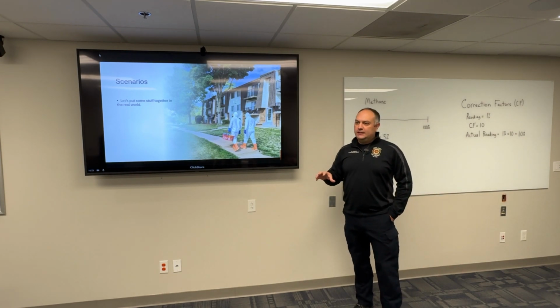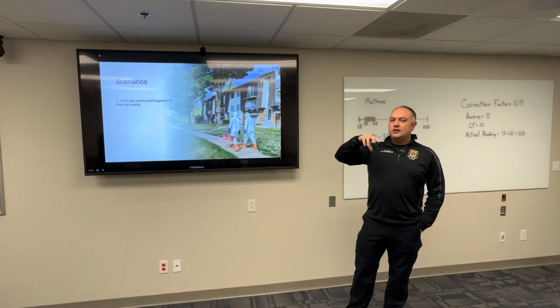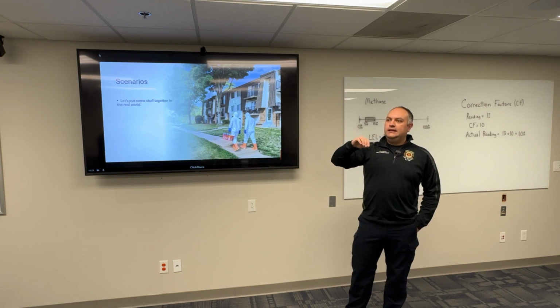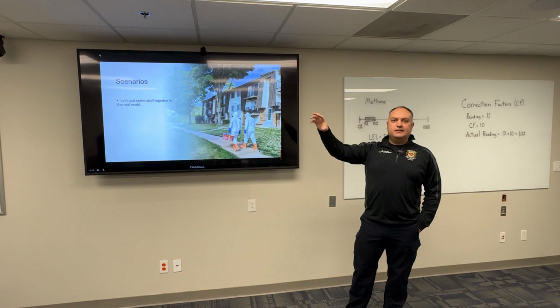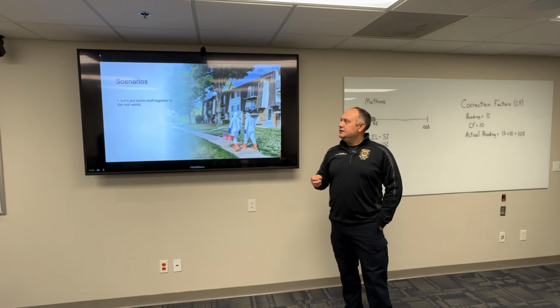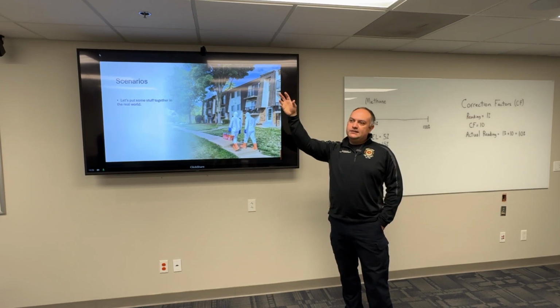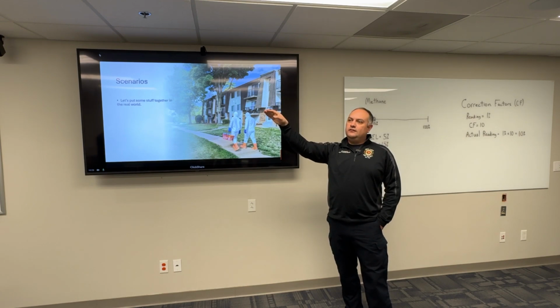Made interface with the first due truck captain, and he said, hey, can you go check the other floors to see what we got? I'm not real sure what's going on yet. So we did that, and as we worked our way up towards the 3rd floor, we started getting increased readings. Increased on the 2nd floor, and then we get to the 3rd floor, and we got up to, I believe it was around 200 or less parts per million of CO. So went up to the 4th floor, they decreased a little bit, so our problem was on the 3rd floor.